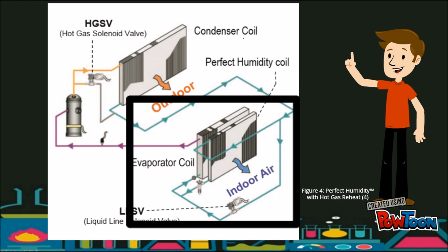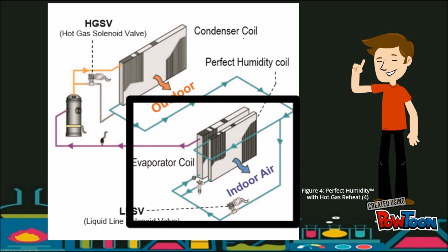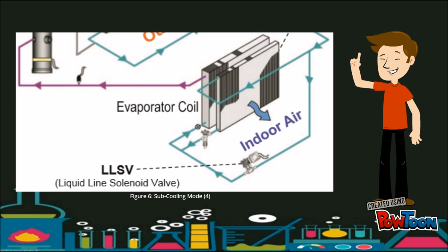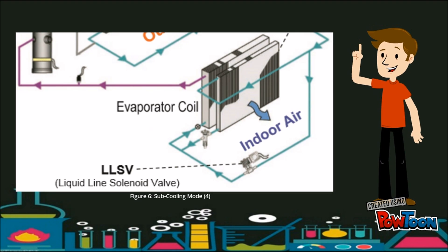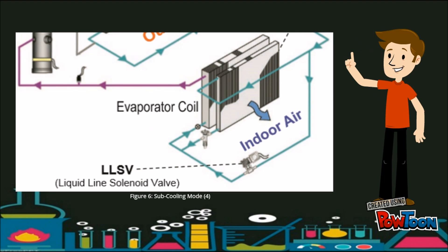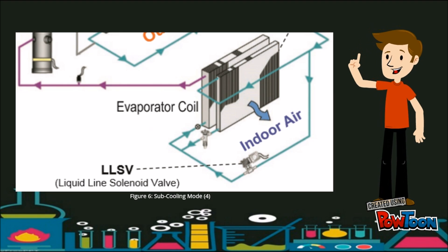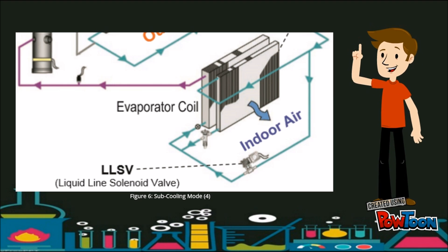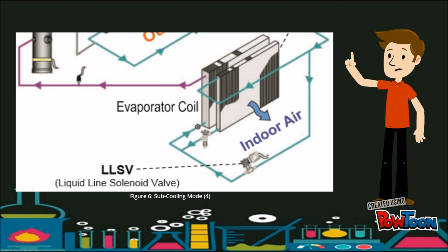Downstream of the condenser, and then through the evaporator. The indoor air stream passes over the evaporator first, then over the perfect humidity coil, further sub-cooling the refrigerant. This highly sub-cooled refrigerant is then fed to the evaporator coil, creating a colder evaporator coil surface.